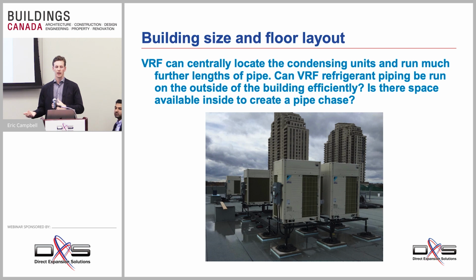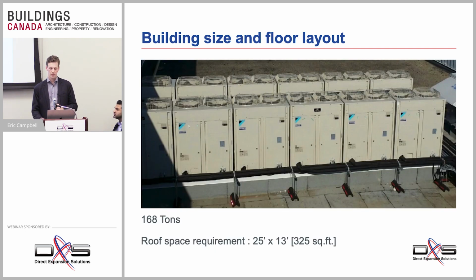And if it's a building that's electrically heated with baseboard heat, doesn't have any sort of hydronic system, it wouldn't have had the infrastructure to hold those pipes that you might be replacing with refrigerant pipes. So now you need to take space away from somewhere else. So that's all considerations, things to keep in mind when you're looking at a VRF solution. You need to have space to run those refrigerant pipes. However, again, these outdoor units are very large and efficient. And so you can do a lot of heating and cooling in a limited amount of space, and you don't need to build any sort of mechanical room or anything like that on the roof to house them.